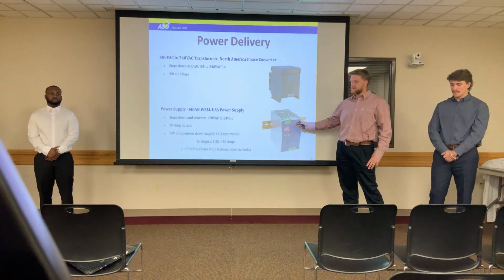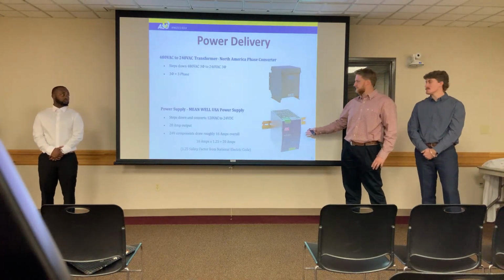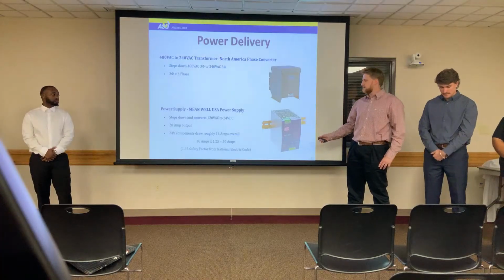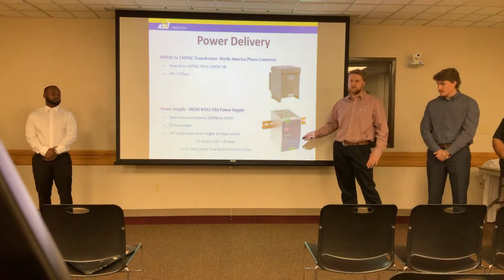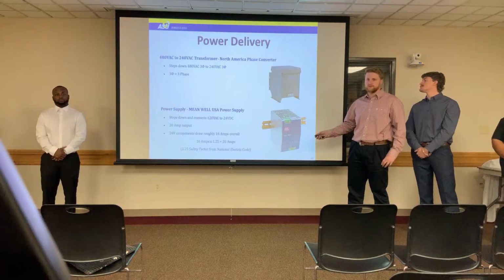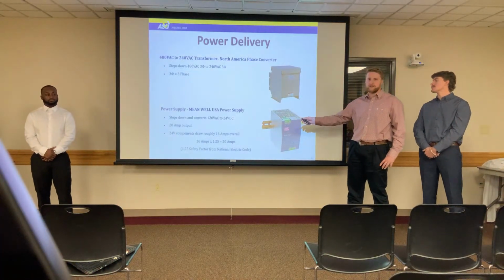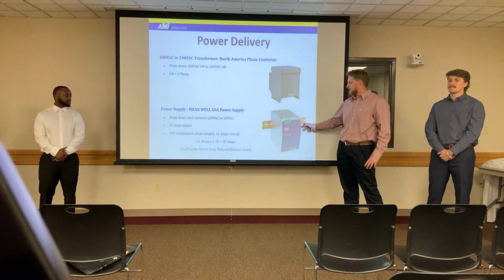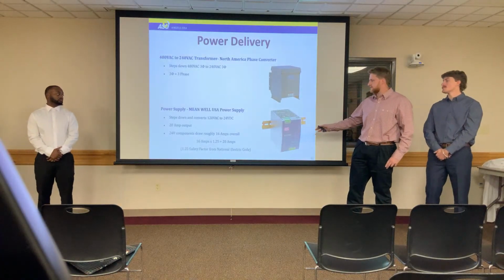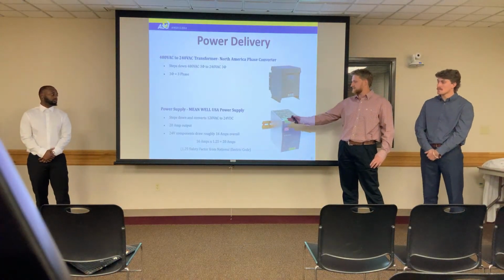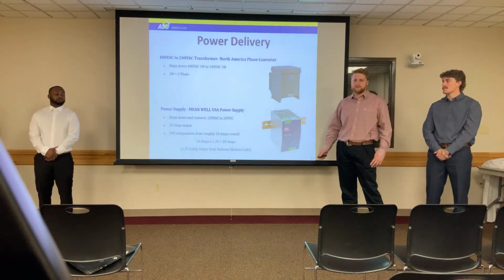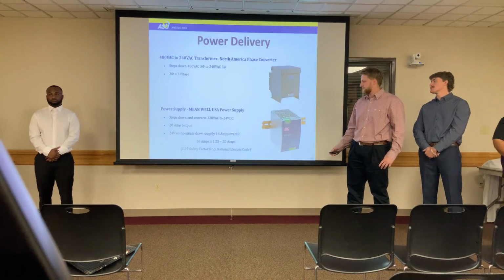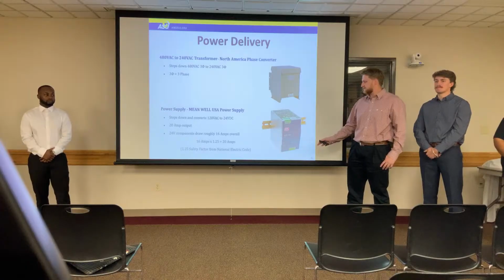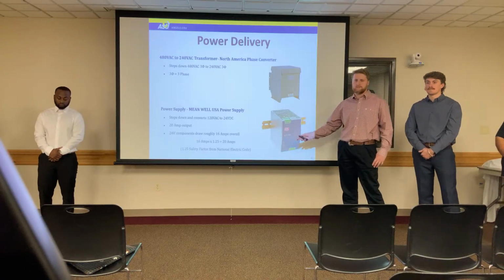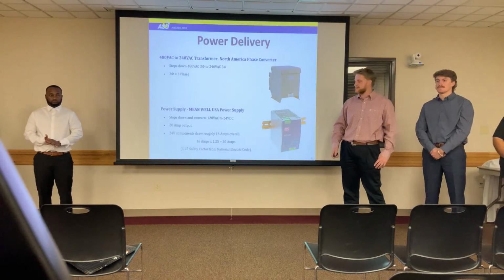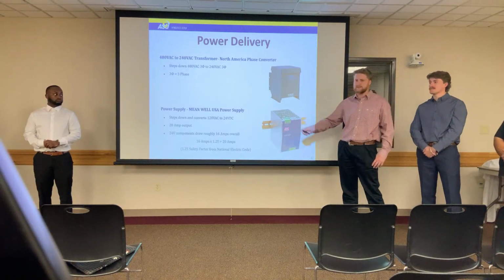Again, we had to lower even more to 24 volts, so we are using a power supply. This will step down 120 volts into 24 volts of direct current, and I'll explain how we got 120 in a second. This will be outputting 20 amps of current. We determined that because our 24 volt components are drawing around 16 amps, and in order to safely operate those, the National Electric Code recommends 1.25 times that amount of current. So that's why we went with 20 instead of 16.